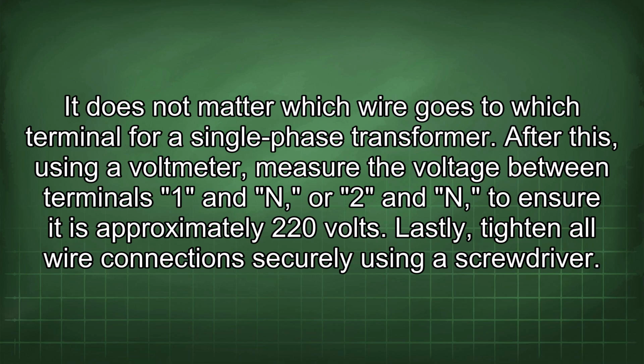After this, using a voltmeter, measure the voltage between terminals 1 and N, or 2 and N, to ensure it is approximately 220 volts. Lastly, tighten all wire connections securely using a screwdriver.